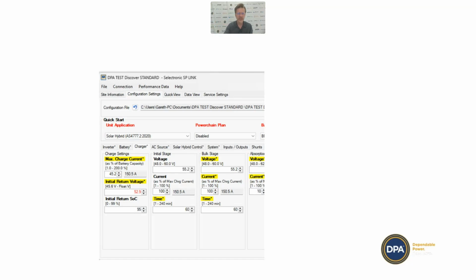And then you're going to adjust this setting down here, which is max charge current as a percentage of battery capacity. You want to set that to about 45. That's going to adjust the charge current down to about 150 amps. And there's a good reason for that.